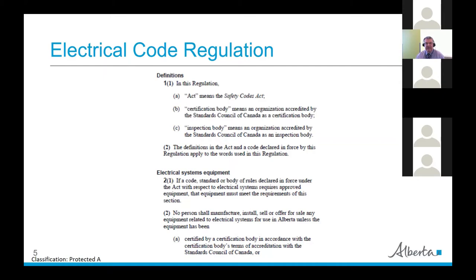Item two says no person shall manufacture, install, sell, or offer for sale. A lot of RSCOs will think of rule 2-024 in the code with regards to approval of electrical equipment. This goes above and beyond that, and that's in the regulation. Anything in the regulation overrides a code. It doesn't just talk about install — Part 1 is an installation code — it also talks about manufacturing, selling, or offering for sale.